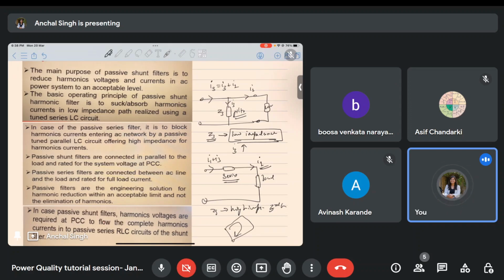But the main difference is that when we design shunt compensators, we design it in such a way that it offers low impedance. That is why we call it absorbing the frequencies. Whereas the series filter is blocking the third harmonic component by offering high impedance. So this is the difference between the two. Here the series filter is blocking, and here the shunt filter is absorbing. So they are not actually the same.